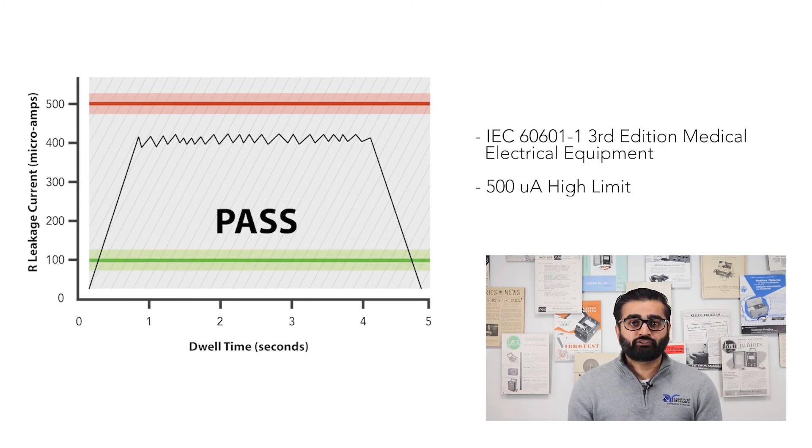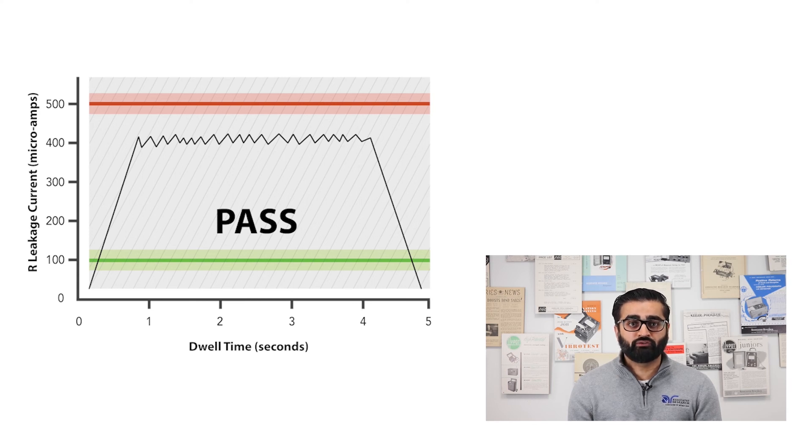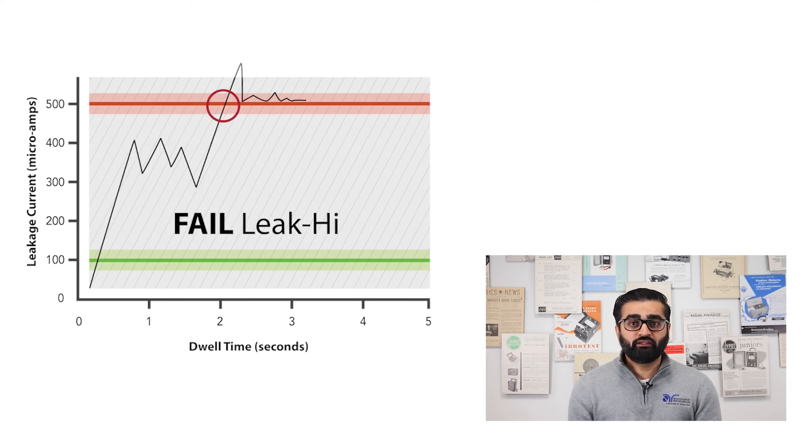For leakage current testing, the standard 60601-1 requires a certain leakage current value to be below 500 microamps. Again, this gives us the high limit value which should not be exceeded in order to be considered a pass according to the standard. If the leakage current is exceeded during tests, the equipment will indicate a high limit failure.